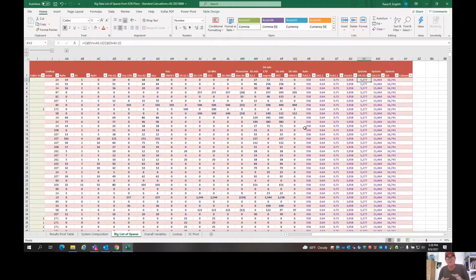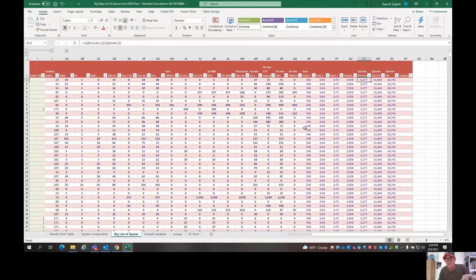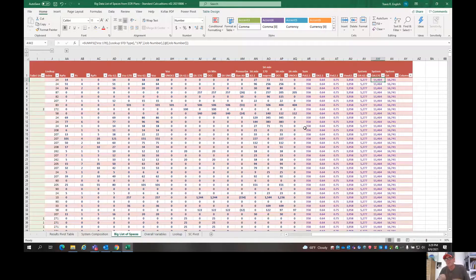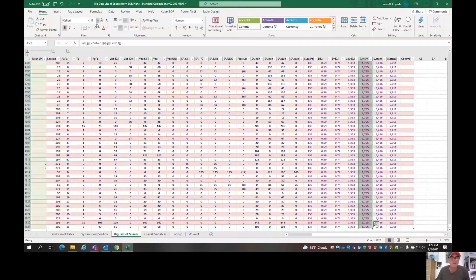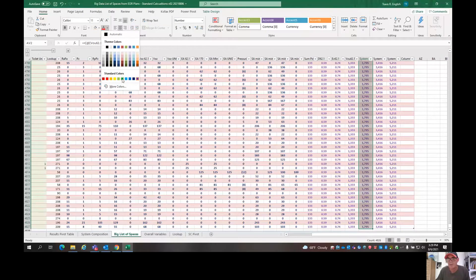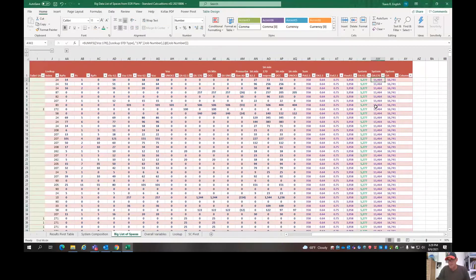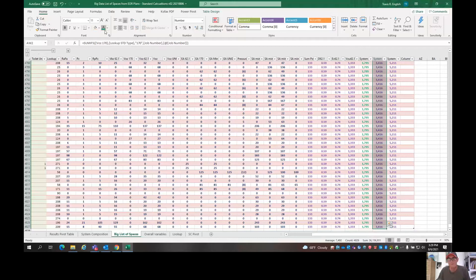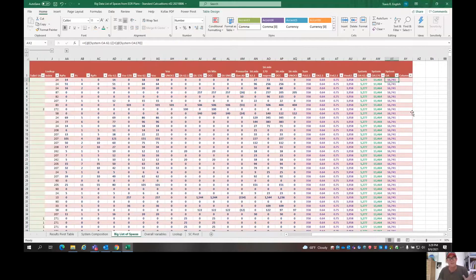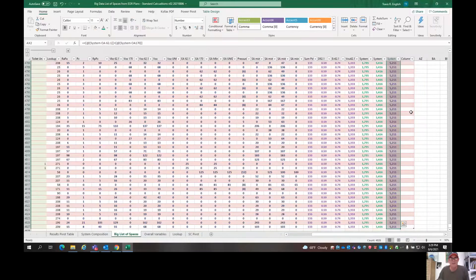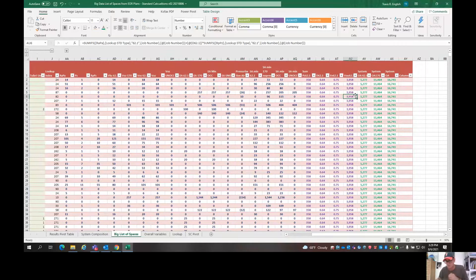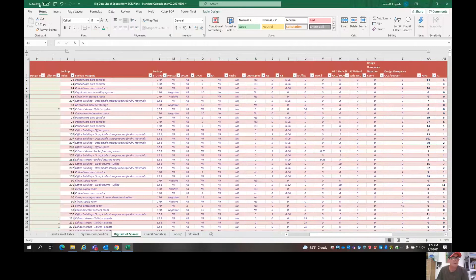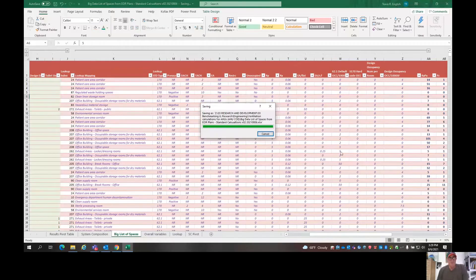Then you do a summation of all of the, oh no, this is just the division to get the system outside air for the 62.1 spaces within the same system. Then we sum up all of the 170 spaces inside the same system. So this is basically the total outside air. I'm going to change the color of this to kind of a green. So that's the sum of the 62 outside air. This is the sum of the 170 outside air within the system. And then you just add those, you literally just add those two together to get the outside air requirement at the system. So that's how the calculations work. You can pause and rewind that video for however much of that you want to see or see as often as you want. Press save here and then I'll show you some of these results.